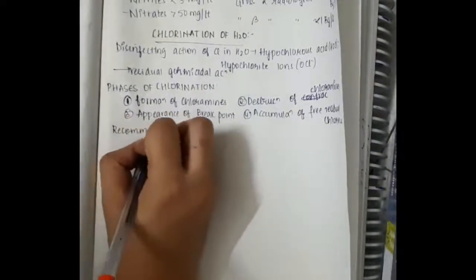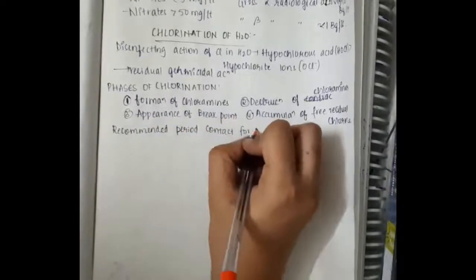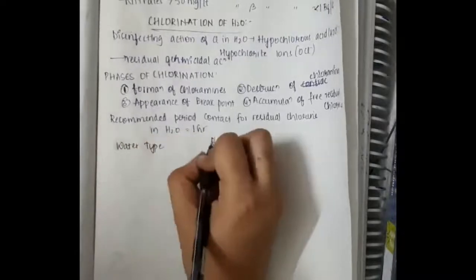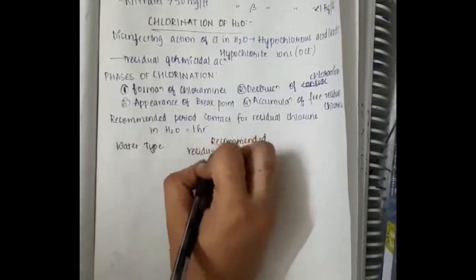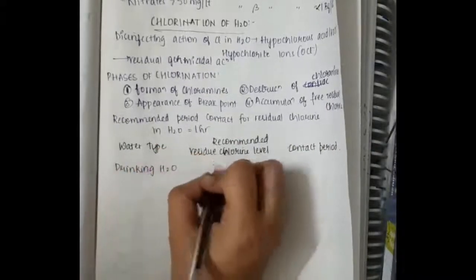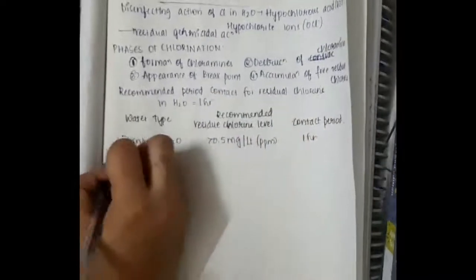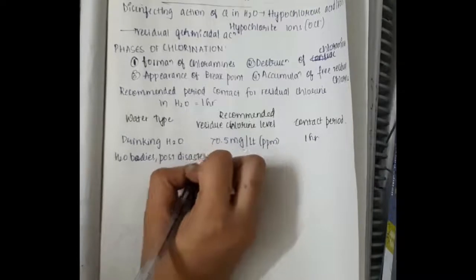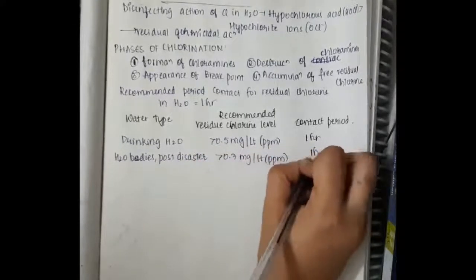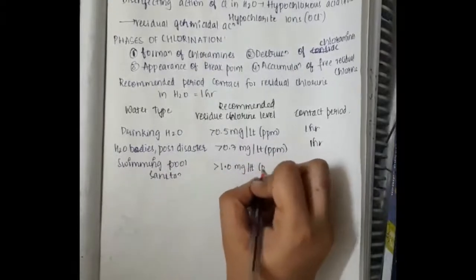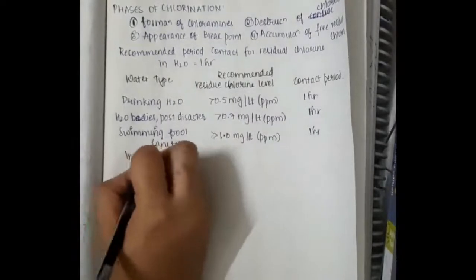The recommended period of contact for residual chlorine in water is around 1 hour. The recommended contact period and residual chlorine level depends upon the type of water. Drinking water requires more than 0.5 mg per litre of residual chlorine for a contact period of 1 hour. Water bodies post-disaster require more than 0.7 mg per litre of chlorine for a contact period of 1 hour. Swimming pool sanitation requires more than 1 mg per litre of chlorine for a contact period of 1 hour.